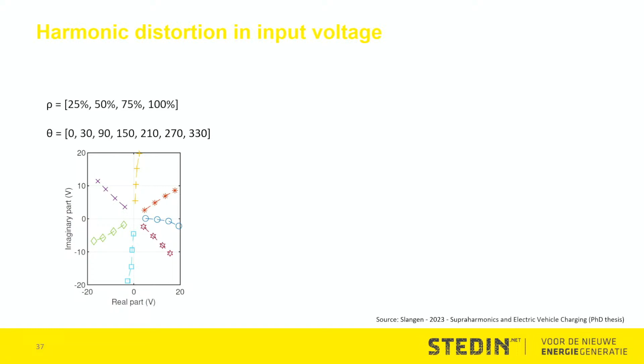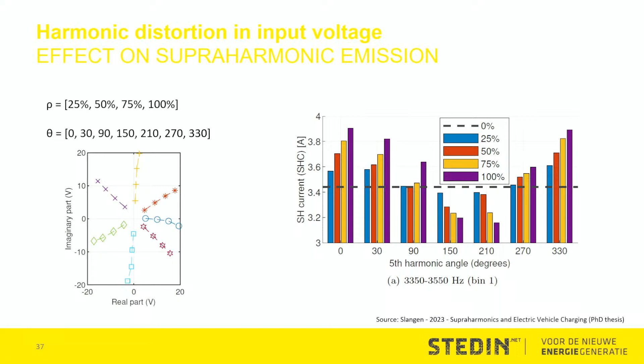That's what we did in the research. What we saw was that this emission, which we first thought was constant, is not constant at this point. Depending on the angle and amplitude of the injected harmonic, the emission changes between 3 and 4 amps. So depending on what is in the background voltage harmonics, this also changes the emission of the device connected to it, and not only at the voltages we inject, but also at other disturbance components present for this device.